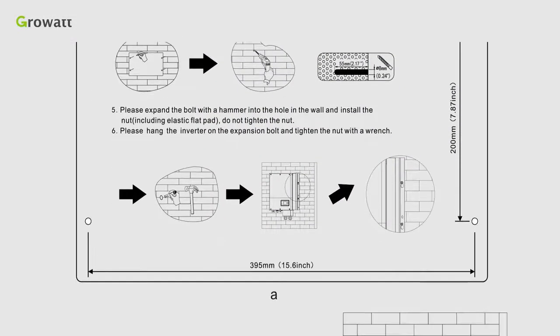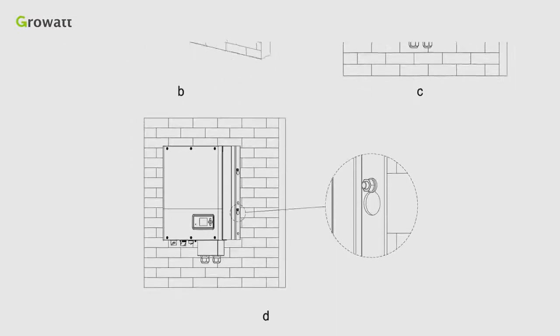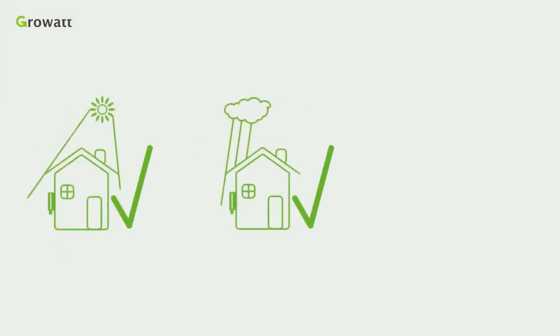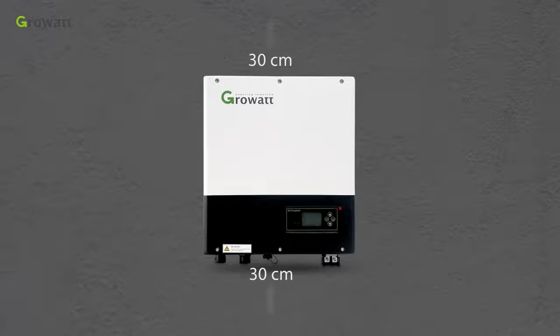Follow the location requirement on the manual to install the inverter in proper places. It is suggested to install the inverter under the shelter, avoiding the direct sunlight and rain. The wall should be stable. Airtight cabinet is prohibited.